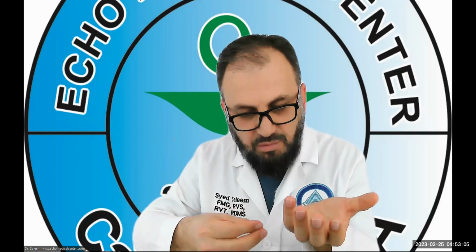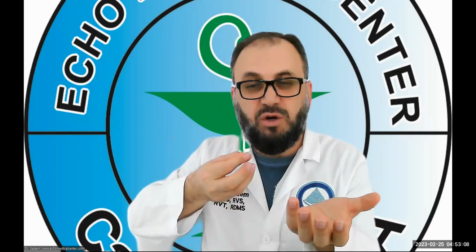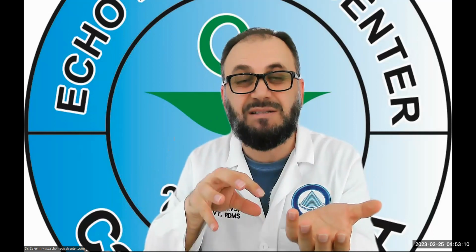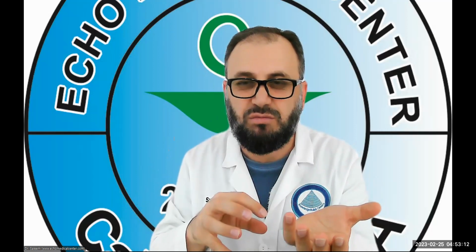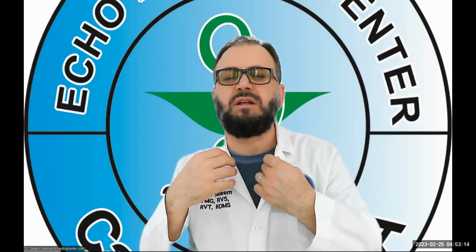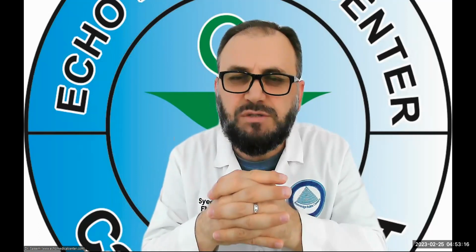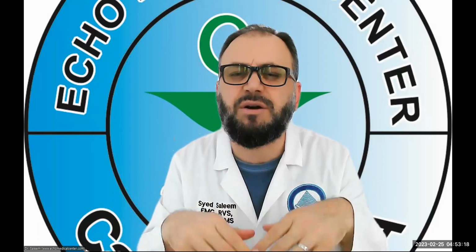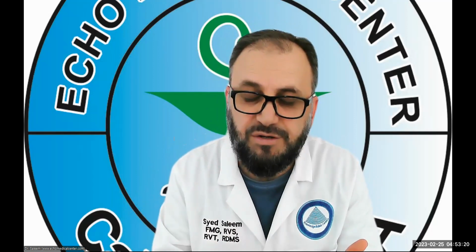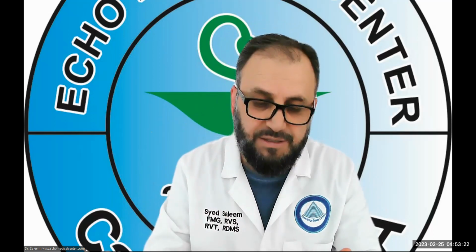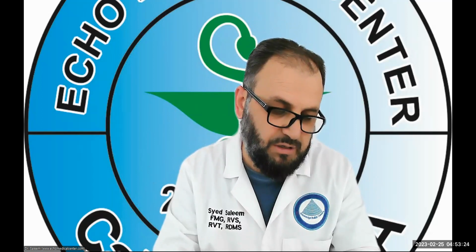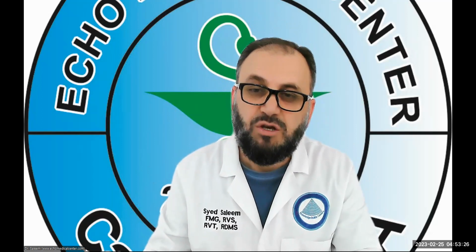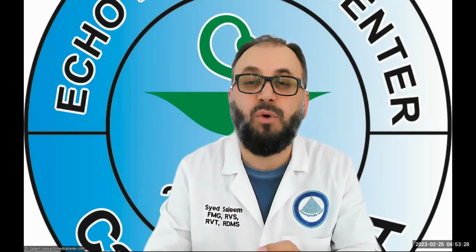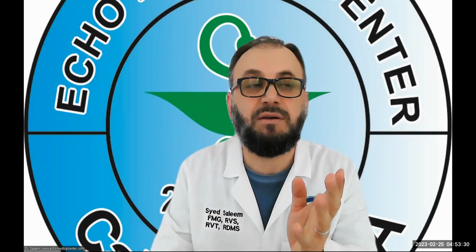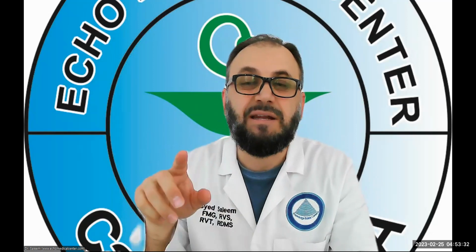You see it very hyperechoic, and that hyperechoic area might seem to represent a very stiff tissue, like the molecules are too close to each other, like a hard tissue. But it's not hard tissue. Another reason might be, if you're looking at the focus, where the focus is, most commonly we get that artifact. It's called focal enhancement artifact.